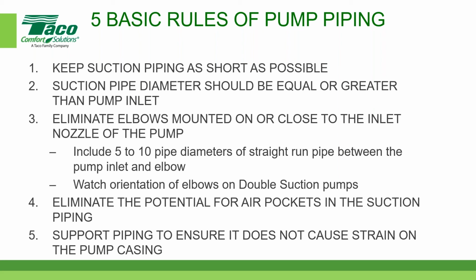They're always important: keep suction piping as short as possible, don't have it too long. The diameter of pipe from the suction should be equal to or greater than the pump inlet. So if it has a 6-inch pump inlet, don't bring in a 4-inch pipe and step up to 6 — you want 6 or greater coming into it. And try to eliminate as many elbows on or close to the inlet nozzle of the pump as possible.